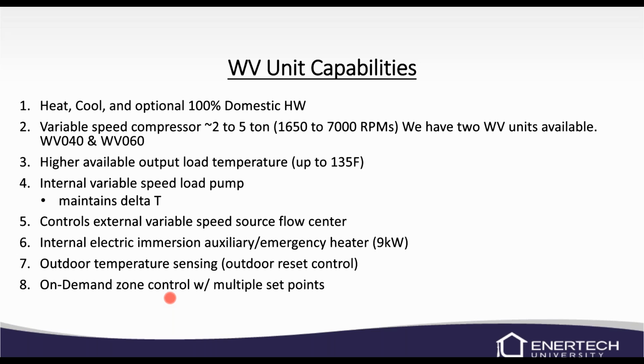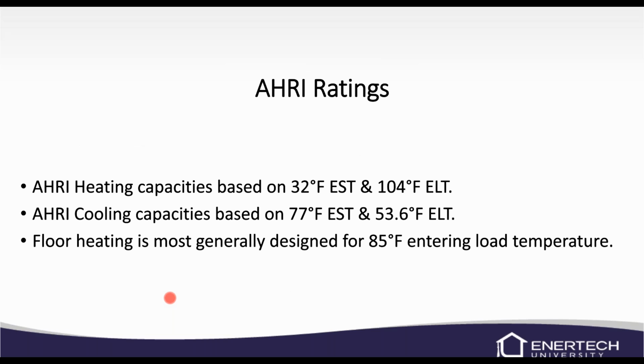What that means is we have a control that can handle a radiant call versus a hot water call versus a forced air heating call. So all three of those calls could have different set points as far as water temperature. So we were able to handle all those multiple set points. We base all of our AHRI ratings off of a heating capacity of 32 degree entering source and 104 degree entering load. And in cooling, it's at 77 source temperature and roughly about 53.5 entering load. We normally design our floor temperatures for around 85 to 95 degrees. So this variable speed will work well for that.